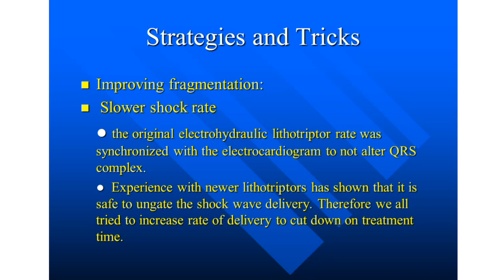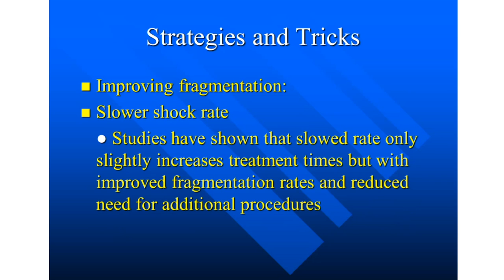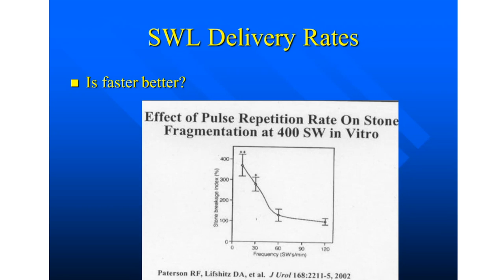And so we started doing that, and we found out that didn't work so well because we weren't getting as good fragmentation, and we were getting more postoperative hematomas and hematuria. So what we learned over time was that a slower shockwave rate was much better. Studies have shown that if we can slow down the shockwave rate considerably, we're going to improve our fragmentation and reduce potential injury to the kidney. This was an in vitro study where they looked at fragmentation rates. And as you can see, obviously, if we could somehow go to 30 shocks per minute, we were going to get much better fragmentation than if we went to 120 shocks per minute. I think for most of us that are doing shockwave lithotripsy now, we've sort of compromised and we're going at 60 shocks per minute in general. Hopefully not too much faster than that.